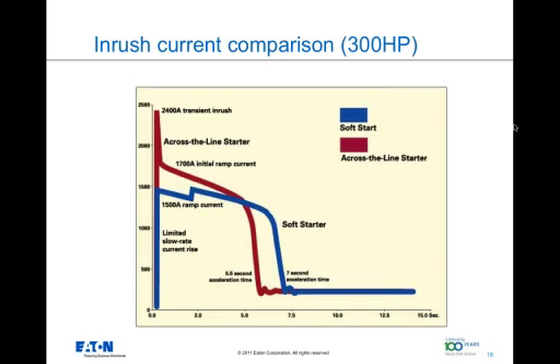This slide is by no means an artist's rendering, but it has two real-time graphs captured in it. The red line is the starting characteristic of a 300 horsepower motor when an across-the-line contactor is used in the system. The blue graph right underneath has the starting characteristic of a motor when a soft starter is used. As you can see, the current draw reduces from 2400 amps to 1500 amps when a soft starter is used. That is a reduction in current of about 38%.